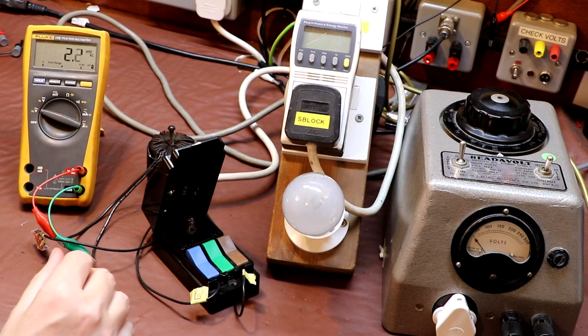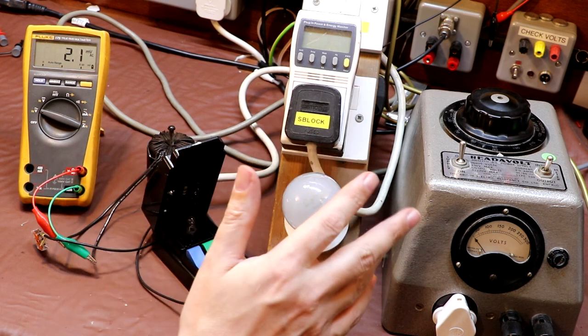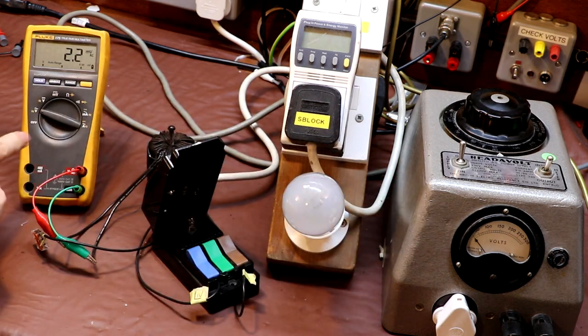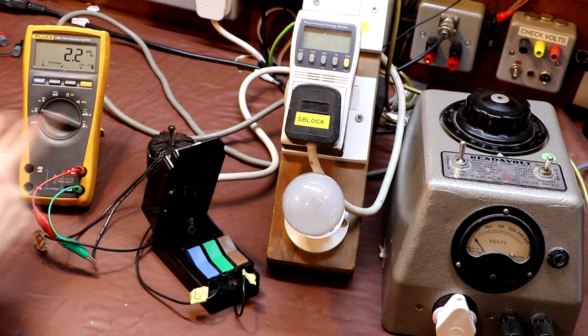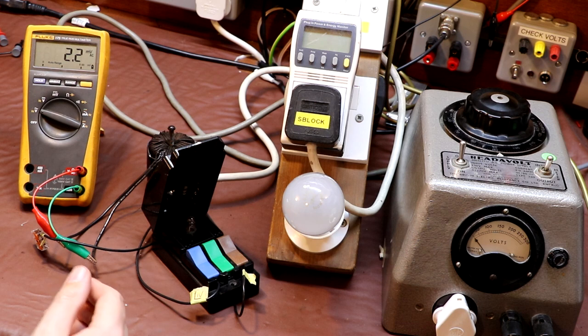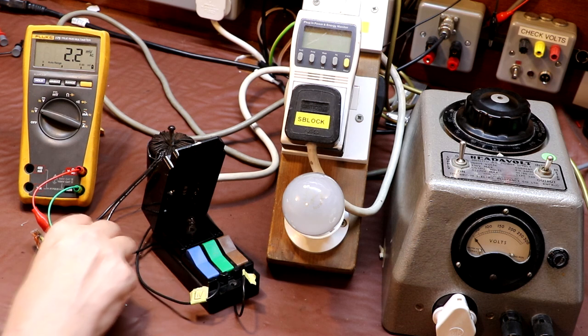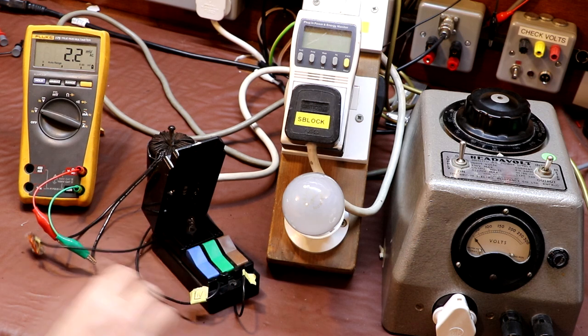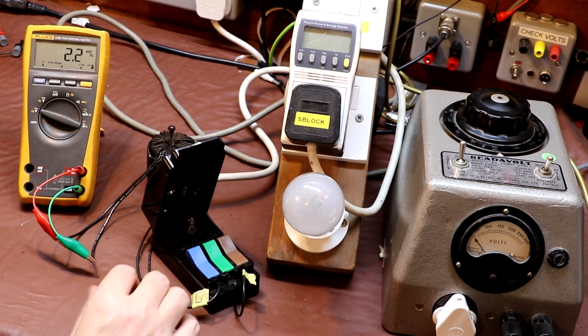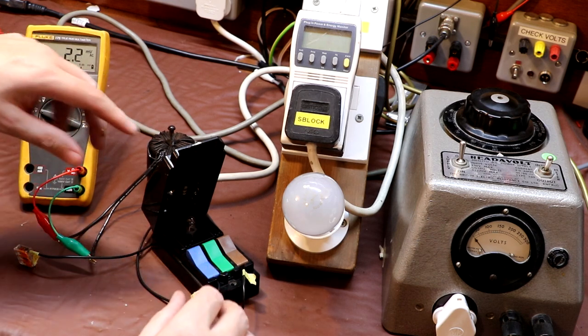Now we've got no load on the transformer, but we'll wind the voltage up to 250, see what the secondary voltage is, and divide the primary voltage by the secondary voltage. That's going to give us the turns ratio, which is a nice little characteristic of a transformer. It's nice to know.